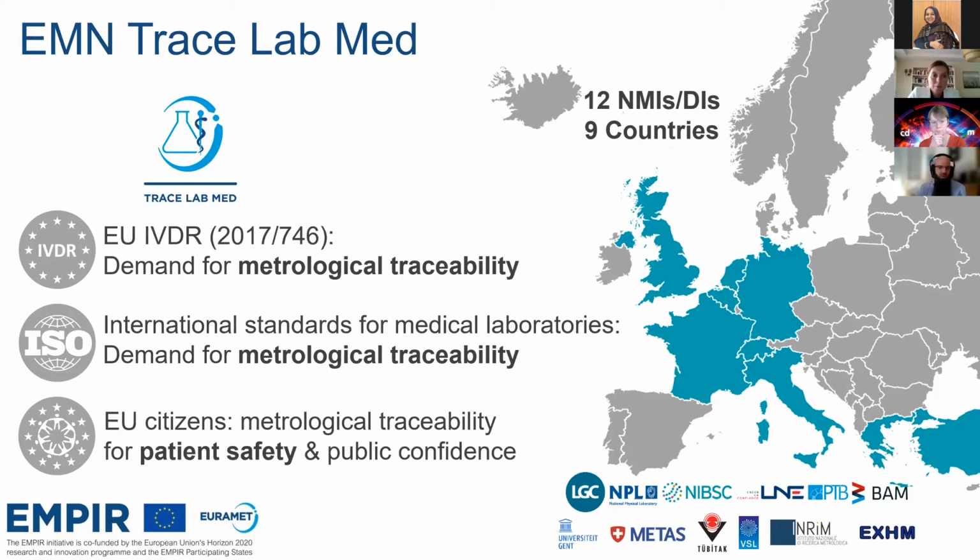And this is a standard that obviously needs to cope with the fact that traceability to the SI is only realized for a small share of clinical measurements, by referring the trueness in these cases to a lower level of the calibration hierarchy. So this could be, for instance, a manufacturer's working calibrator or selected measurement procedure. And this is then until an internationally agreed reference measurement procedure and/or calibrator becomes available. That small share I'm referring to currently makes up about 10 to 15% of the routinely requested medical tests. And this obviously leads to the risk of poor comparability in many other cases.